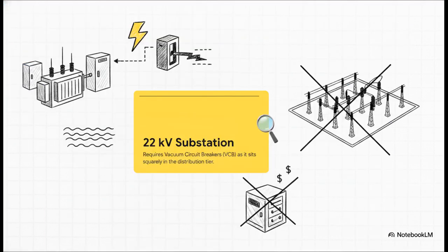Think about it. Well, if you said VCB, you hit the nail on the head, you are exactly right. A 22 kilovolt substation is an indoor distribution voltage facility, which means it sits squarely within the vacuum circuit breaker tier. Specifying GIS in this scenario would mean severely overspending on totally unnecessary technology. And obviously, trying to build an old-school air-insulated yard would just get your design rejected for wasting precious space. So 22 kilovolts means VCB, for sure.